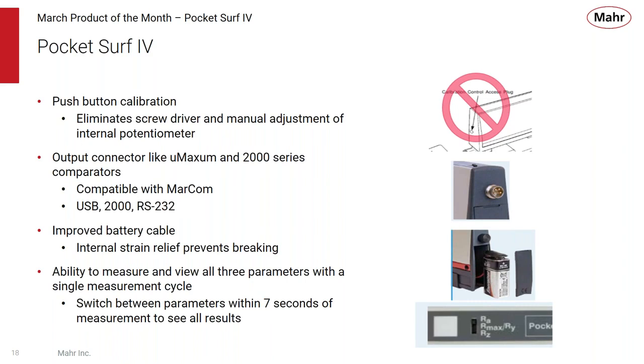Instead of having the old calibration by screwdriver, we did calibration by a digital method today. So that makes it a little bit more accurate and less chance of damaging the system by pushing a small screwdriver through a hole in the side of the product. So it makes it a little bit more robust. We also changed the output connector to be like some of the other Mahr products, like the uMaxum and 2000 series comparators, so that there's a standard cable and it can be used with Marcom now. So a great way of getting data out of the product.